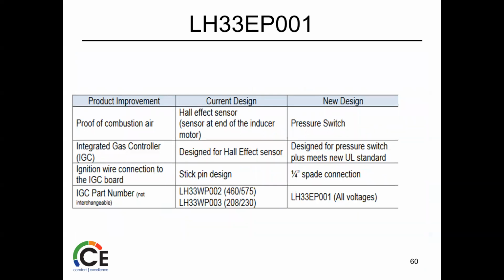So again, it's always looking for proof of combustion, right? In the older units, we used Hall effect sensors. Some of the newer units, they're just looking at RPMs and different things. Pressure switches, integrated gas controller, 1/4-inch spade, which is pretty common for just about everything in HVAC.